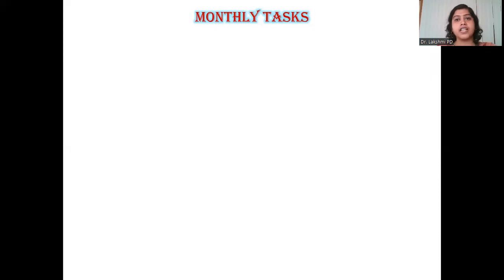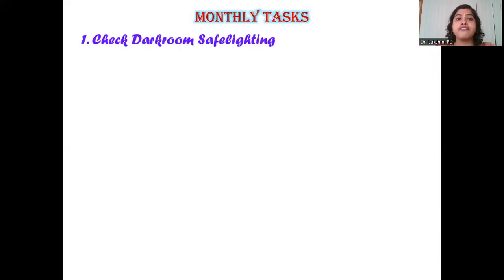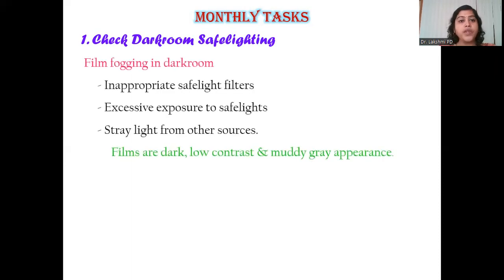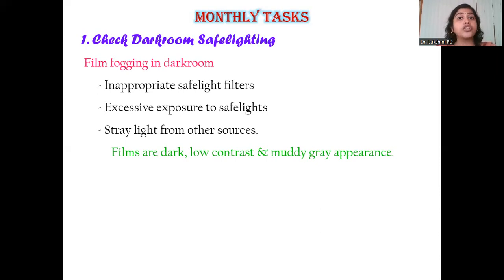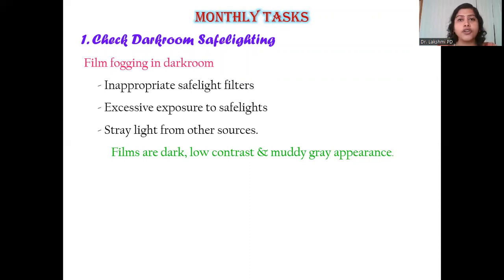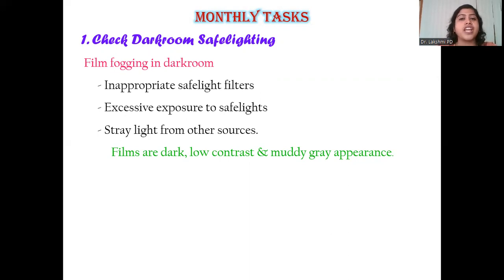Moving on to monthly tasks — tasks to be done at the end of every single month. The first is checking your darkroom safe lighting. If your darkroom safe lighting is not proper, you will get films that are completely fogged — films of low contrast with a very muddy gray appearance, not of acceptable diagnostic quality. Inappropriate safe light filters, excessive exposure to safe lights, or stray light from other sources could be reasons for improper darkroom safe lighting.